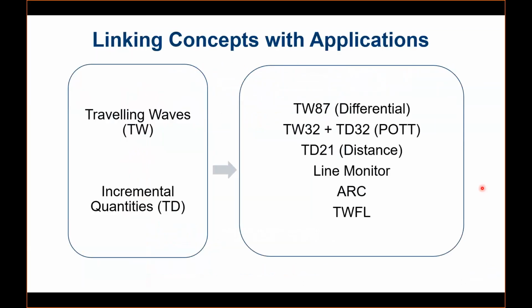First, we will understand the concept of traveling waves. There is one more methodology, which we call incremental quantities: TD quantities and TW quantities. We will understand the basic concepts, and then link them with applications, that is, what we can achieve with these two technologies. Conventionally, we use differential protection for our transmission lines or cable feeders. So we have a new differential element based on traveling waves. Similarly, we use directional permissive schemes to protect our lines. We can use the new technologies to achieve the same conventional things, but with more reliability and more speed.